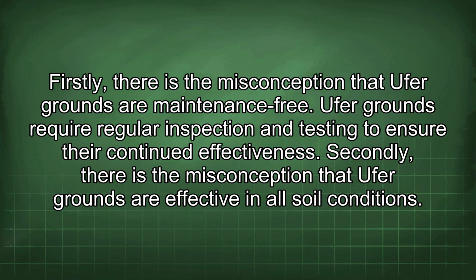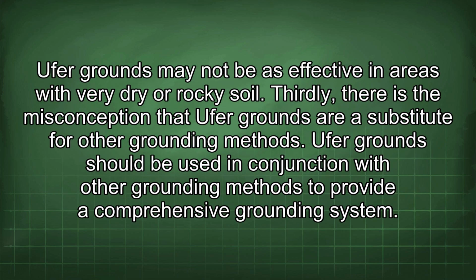Secondly, there is the misconception that Ufer grounds are effective in all soil conditions. Ufer grounds may not be as effective in areas with very dry or rocky soil. Thirdly, there is the misconception that Ufer grounds are a substitute for other grounding methods. Ufer grounds should be used in conjunction with other grounding methods to provide a comprehensive grounding system.